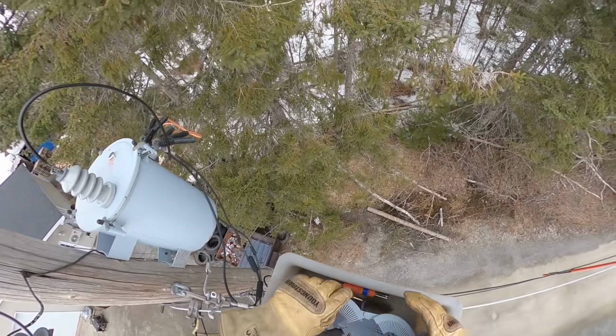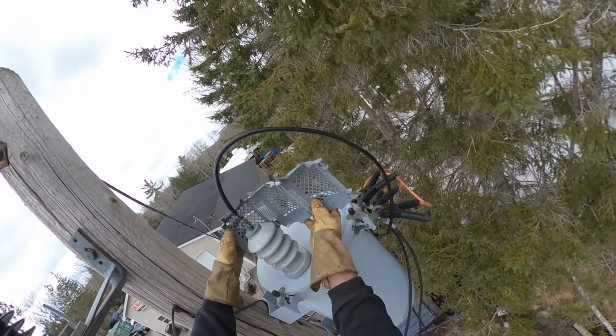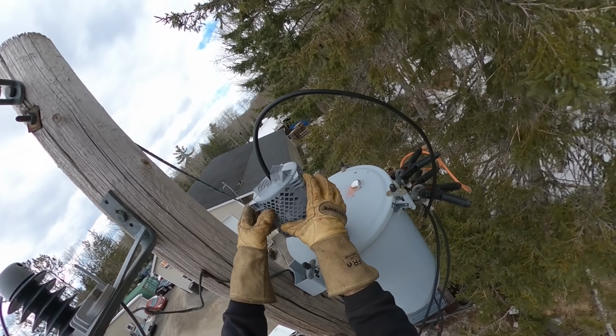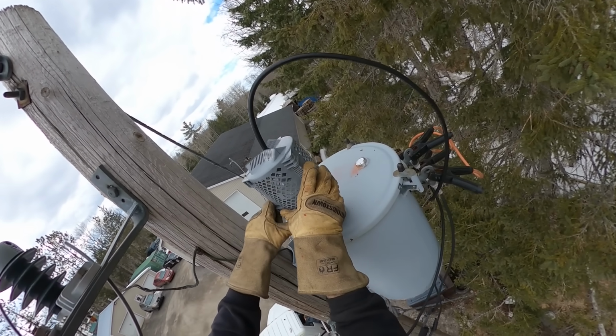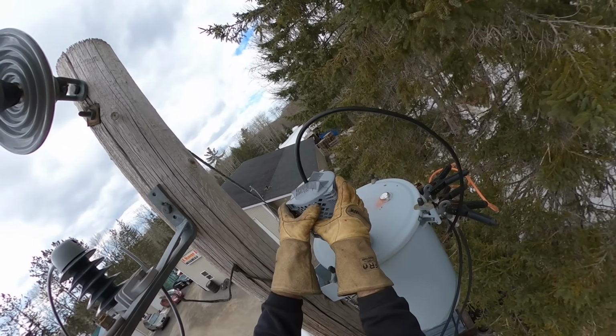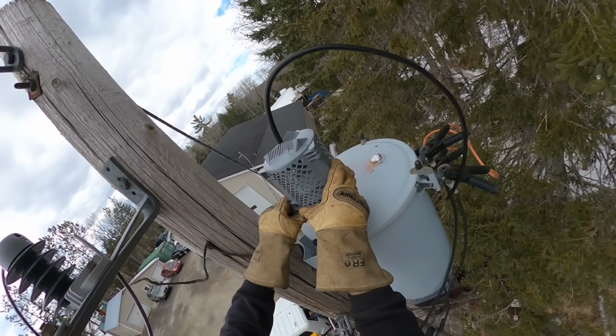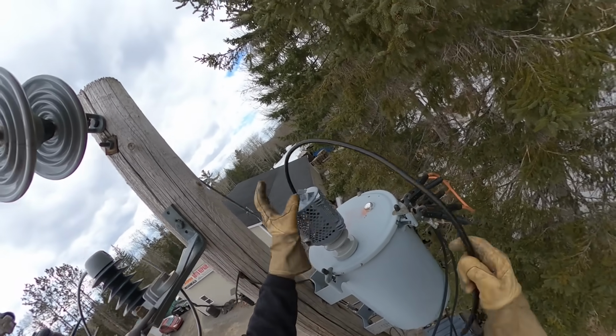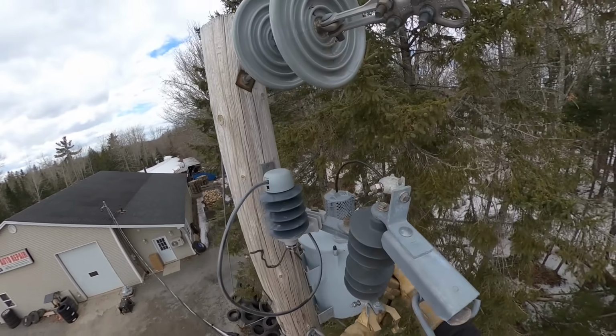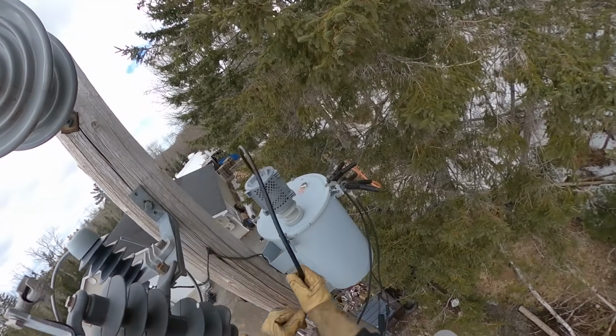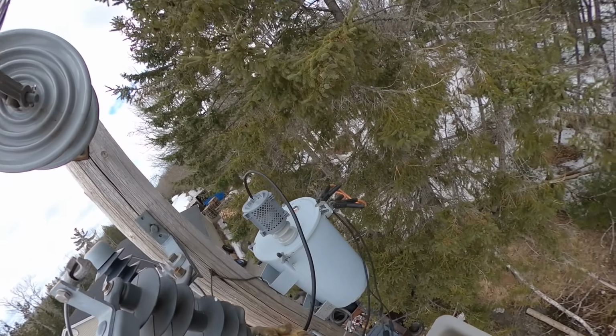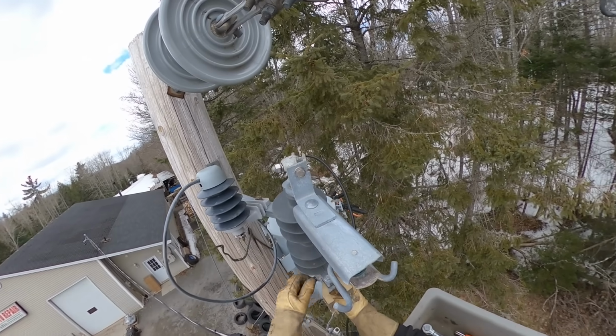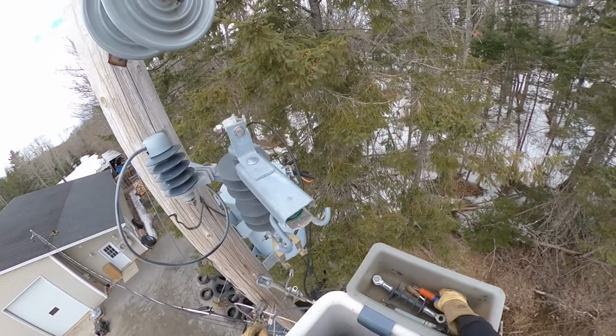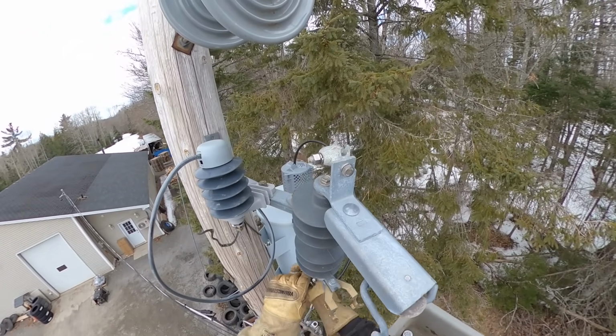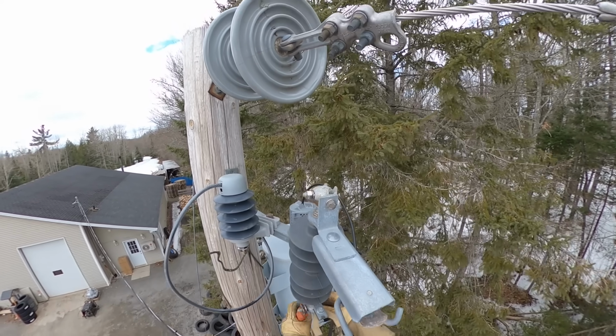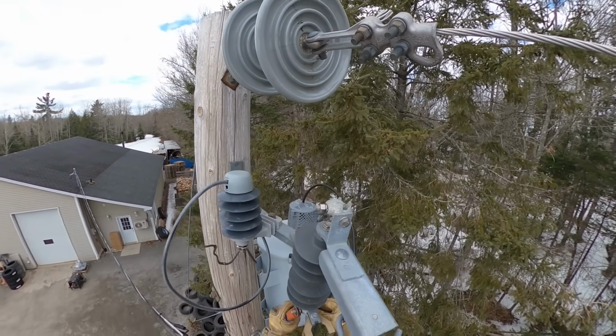There's a few different types. For a regular transformer, it doesn't really matter if you use one of the mesh ones like this or the solid ones. The mesh ones are more designed to look for hot spots with the thermal cam. So if you are using bushing covers or squirrel guards on the bushings of a recloser or any of the equipment in a substation, generally you want to use the mesh type. So there is some open air that you can see that heat coming off of if there's a bad connection with your thermo cam.